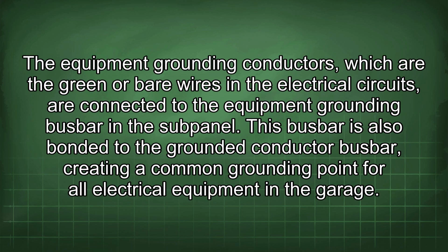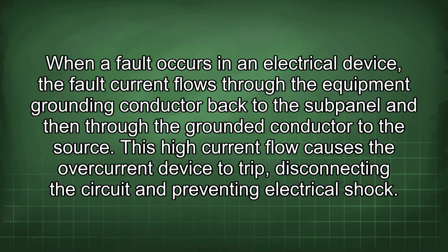The equipment grounding conductors, which are the green or bare wires in the electrical circuits, are connected to the equipment grounding busbar in the subpanel. This busbar is also bonded to the grounded conductor busbar, creating a common grounding point for all electrical equipment in the garage. When a fault occurs in an electrical device, the fault current flows through the equipment grounding conductor back to the subpanel and then through the grounded conductor to the source. This high current flow causes the overcurrent device to trip, disconnecting the circuit and preventing electrical shock.